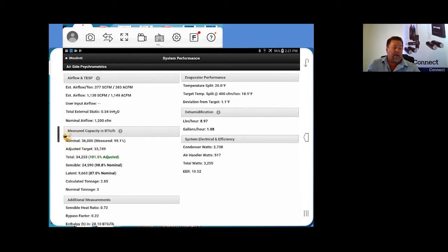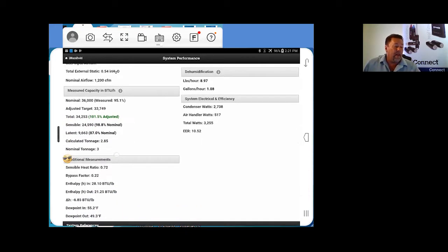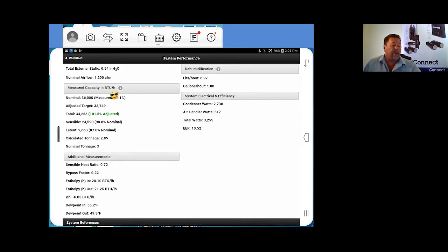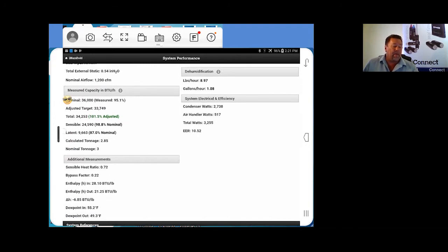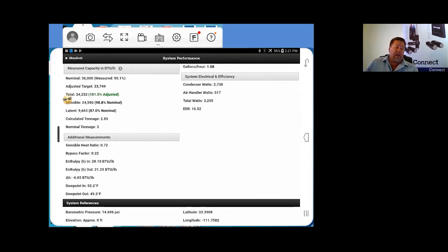Our adjusted target from our conditions is 33,749. We're making 34,253 BTU. So that's 101.5% of the adjusted due to conditions. So this system's running very, very well right now. You've got your sensible, your latent, your calculated total, nominal, your additional measurements here.